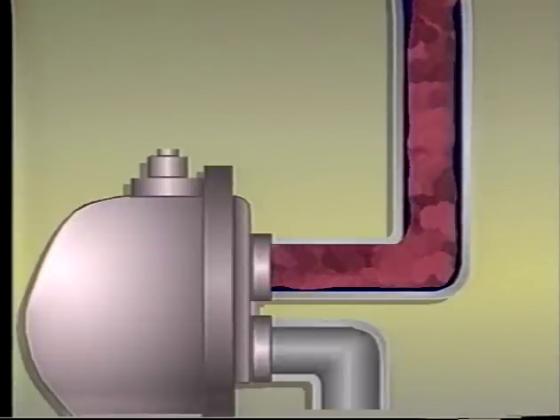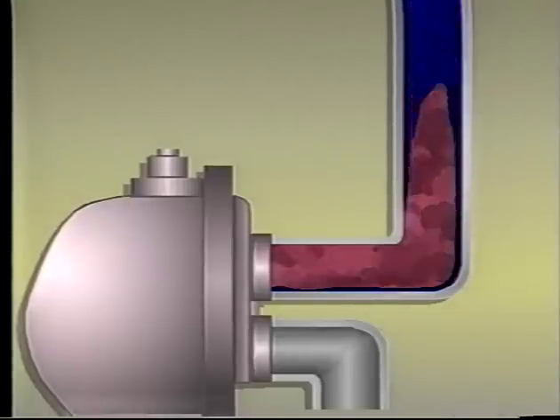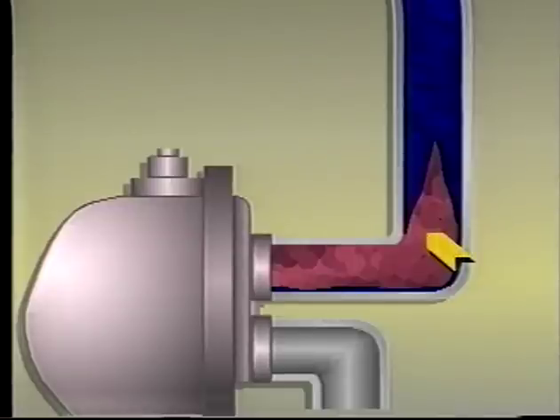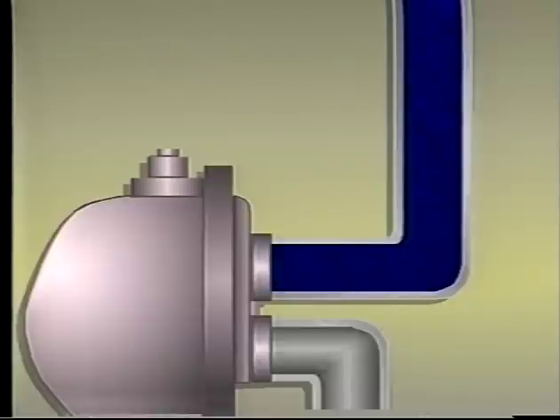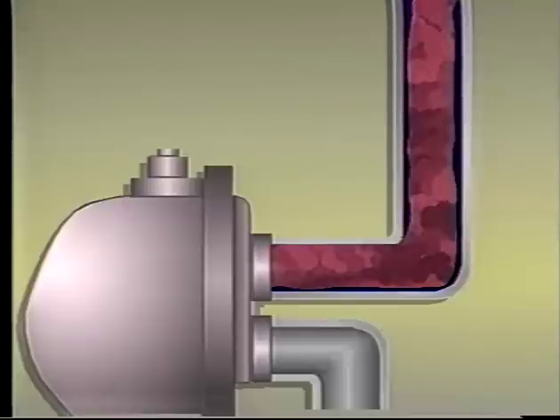The steam flow rate increases if a thermostatic element such as the bellows or wafer in an F and T trap opens. If a slug of condensate seals off the pipe, steam collapses downstream of the seal. Again, a pressure differential forms, and this, along with gravity, accelerates the slug.